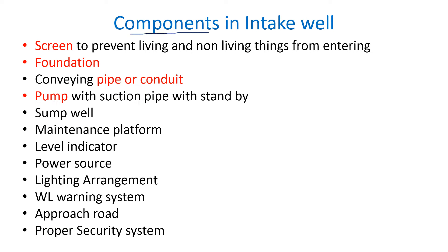In any Intake well, the possible components include: screens — holes provided in the body of the Intake tower to prevent large floating impurities from entering; conveying pipeline or conduits; pumps with suction pipe and standby pump for repair situations; a well for storing water; maintenance platform; level indicator to record water level variations; power source to operate the motor; lighting arrangements; water level warning system; approach road; and proper security system.